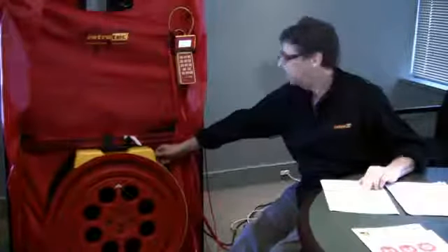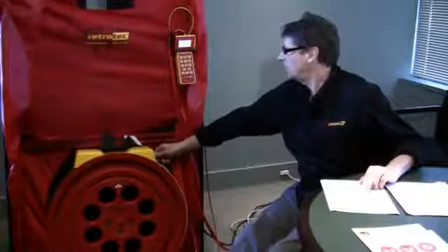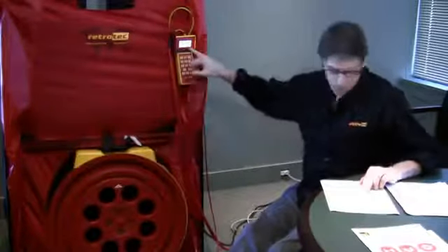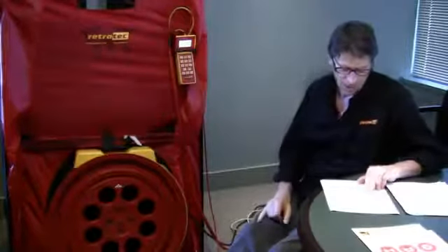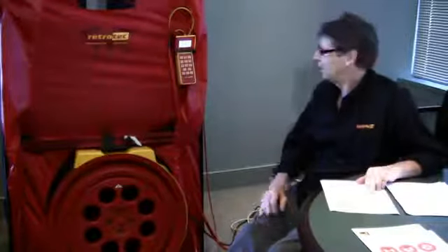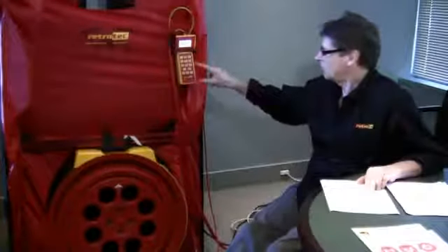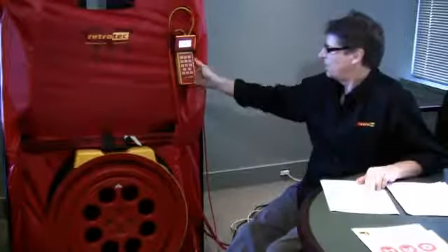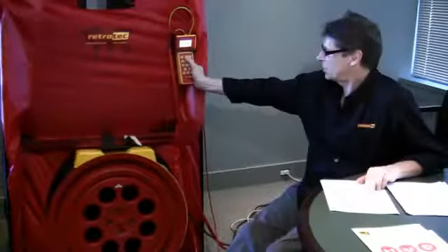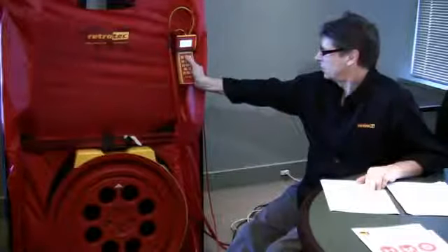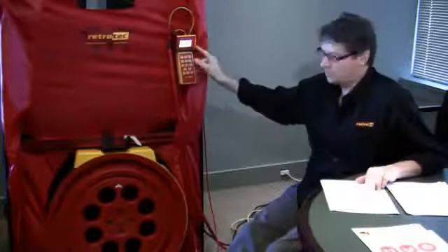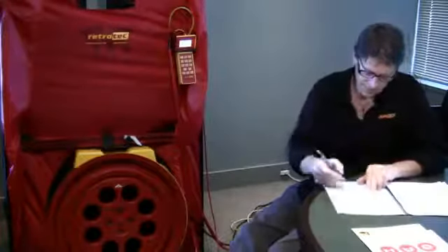We're now going to create a 500 CFM flow rate up here, and then we're going to fool the gauge by changing the range configuration using the range configuration key and see what happens to the flow. So we're going to press this until A appears, and read the flow rate and write it down.